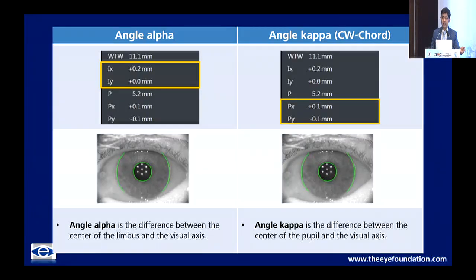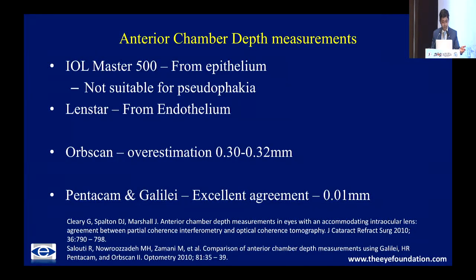Additionally, you also have the angle alpha and angle kappa measurements, which are also very useful, especially when you're looking at premium IOL surgery. Going on to anterior chamber depth measurements, this is very important, especially because most of the 4th and 5th generation formulae look at deriving the effective lens position as a very key indicator for outcomes. So measuring an accurate anterior chamber depth and accurate lens thickness becomes very important in getting the ELP. The IOL Master 500 measures from the epithelium, and it was also not very repeatable when it came to pseudophakic eyes. The measurements were not so accurate, but the other Scheimpflug devices were very good.